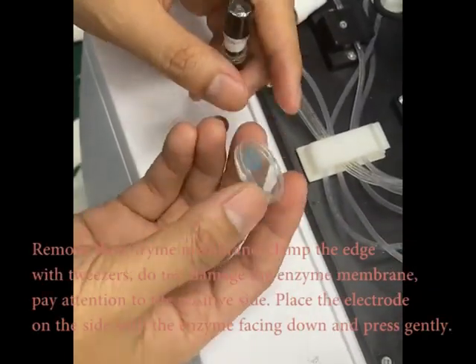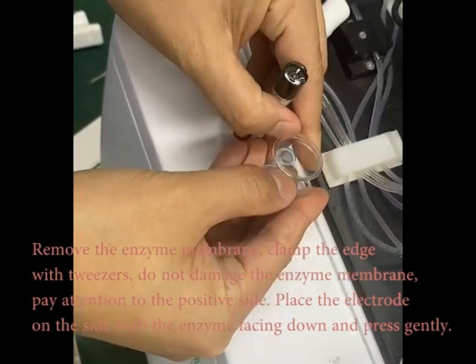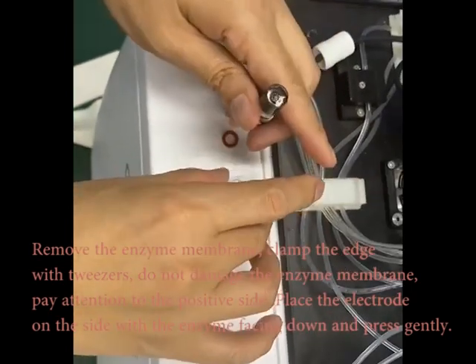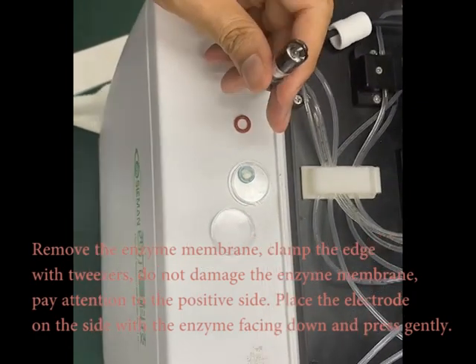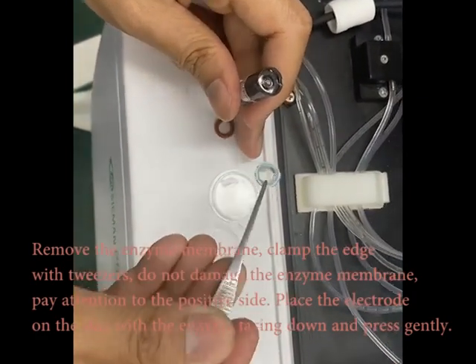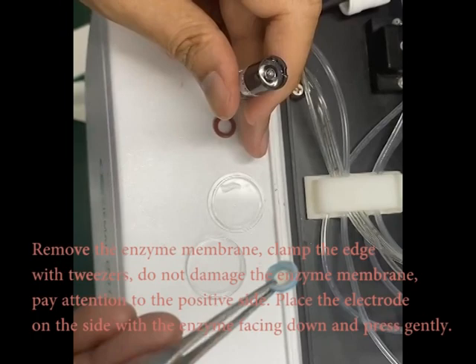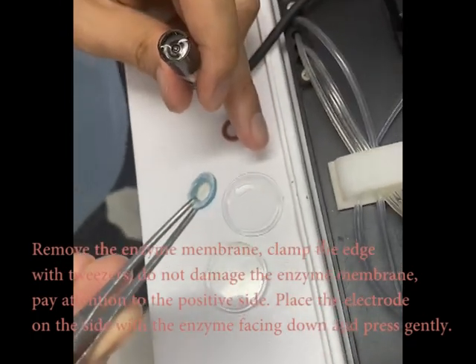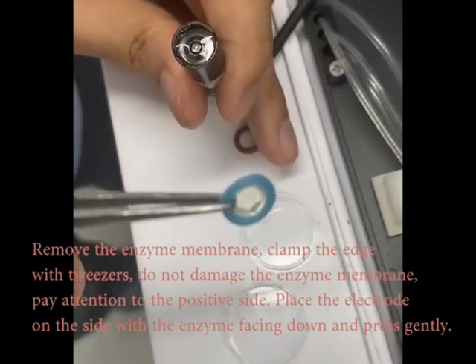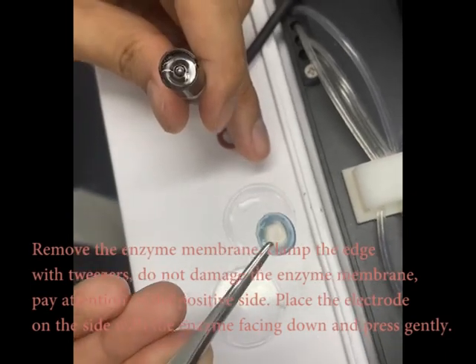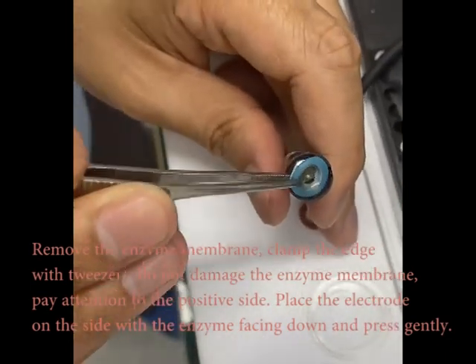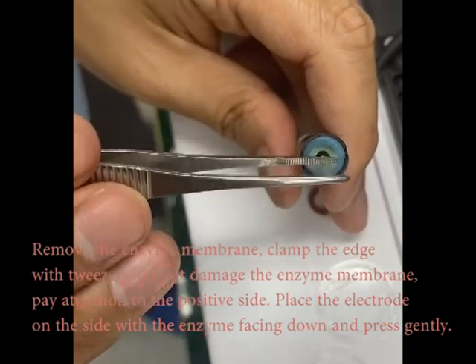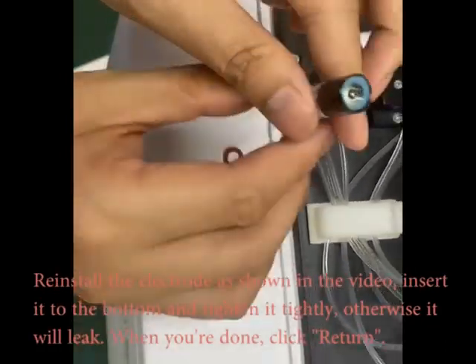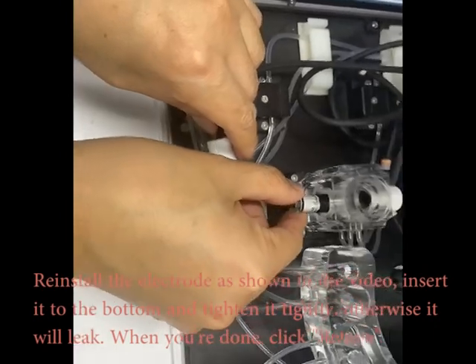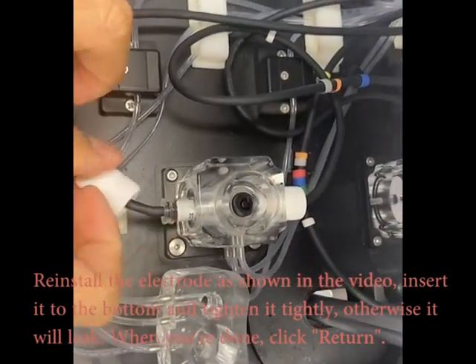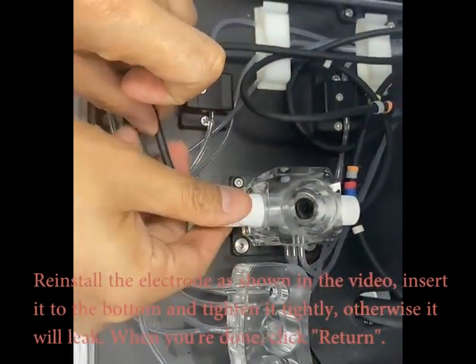Remove the enzyme membrane, clamp the edge with tweezers, do not damage the enzyme membrane, and pay attention to the positive side. Place the electrode on the side with the enzyme facing down and press gently. Reinstall the electrode as shown in the video, insert it to the bottom and tighten it tightly, otherwise it will leak. When you're done, click Return.